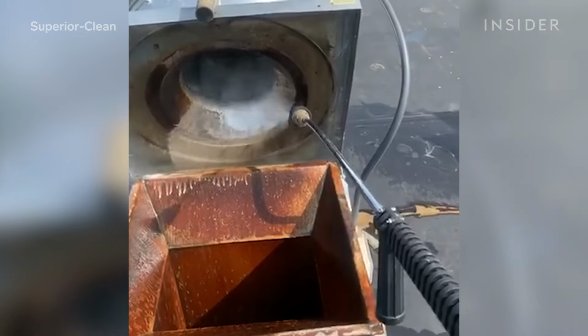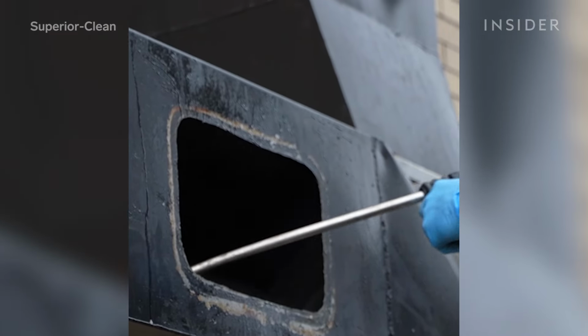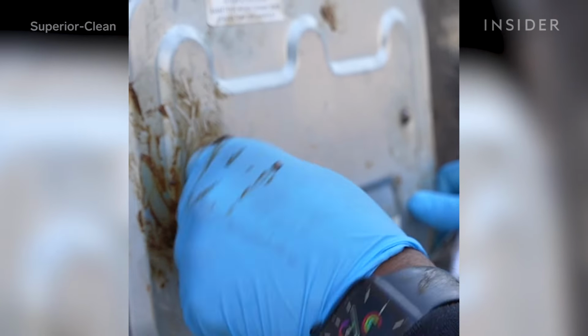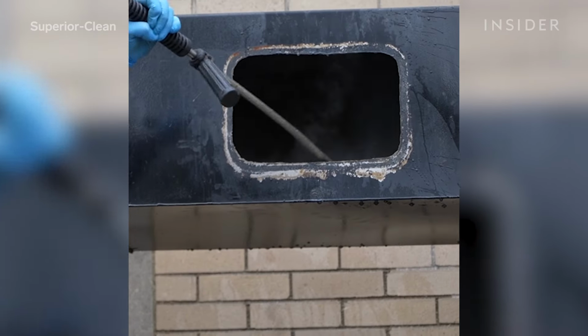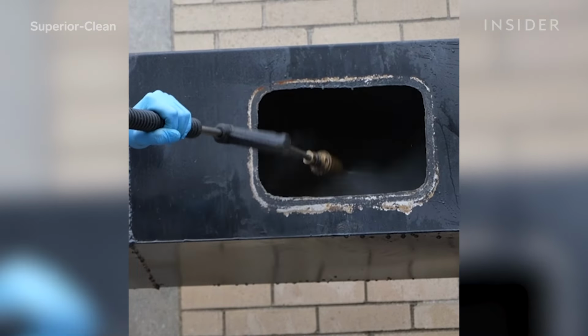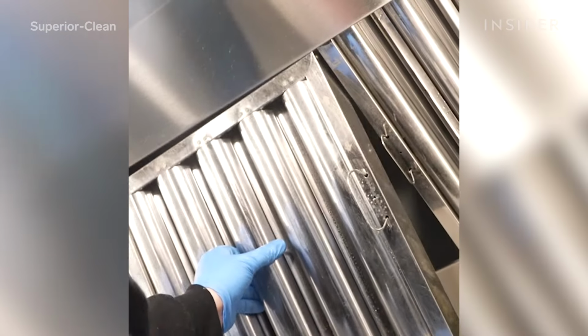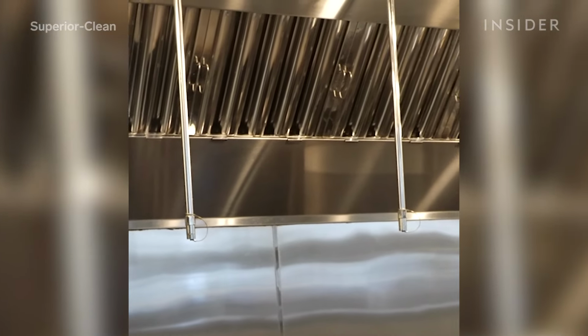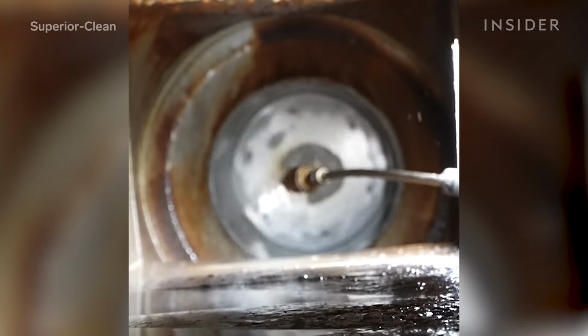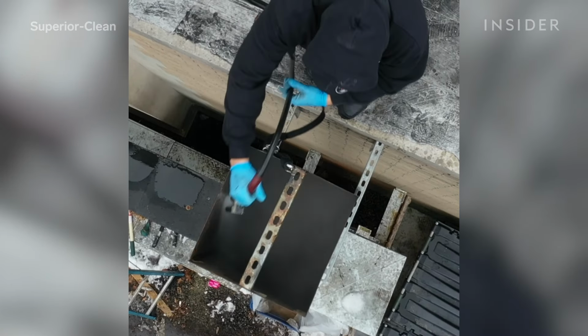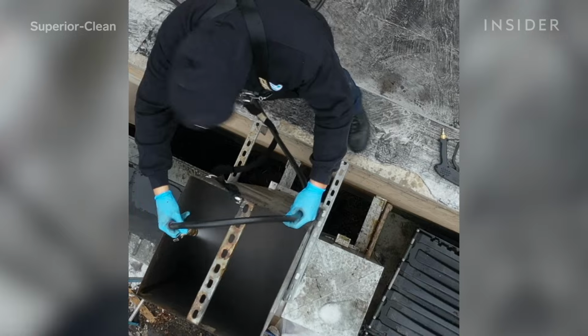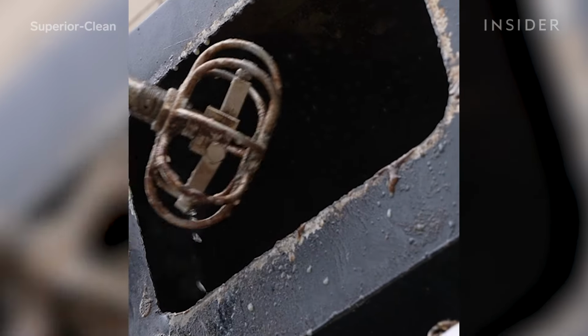It moves down vertically to a horizontal 90 bend, and that's where the inline exhaust fan sits. To the left of the system, there are two access panels, which give you the accessibility to scrape, degrease, and steam clean inside of the ductwork to make sure that the system remains bare metal. And that leads you into the kitchen where the exhaust hood is. Exhaust fans are generally the dirtiest part of the kitchen exhaust system due to it being the last point of passage before it exits.